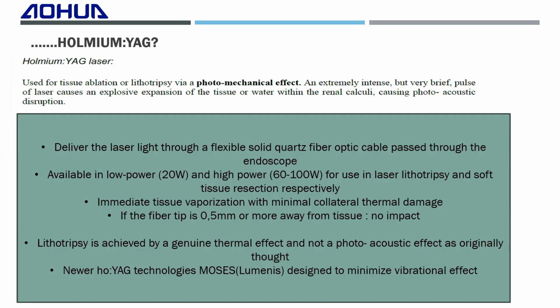So we have an immediate tissue vaporization with minimal collateral thermal damage. This is a huge advantage, the fact that you don't have thermal damage. Okay, and you have to be aware that with a YAG laser, the HO YAG laser, if the fiber tip is 0.5 millimeters or more away from the tissue, then you have no impact. You have to be in constant direct attachment to your urolith, okay?